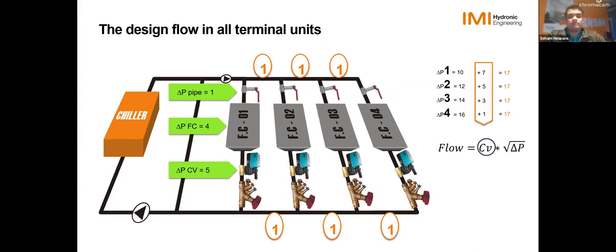And as I mentioned, it's based on what valve you're picking. It's the CV of the valve. It's the opening that you have on your valve and how much you restrict it. So, the closer you get to the pump, the more restrictions you're going to add, of course, because you want to have higher pressure drop. You need higher pressure resistance closer to the pump, because that's where you're possibly going to overflow. So, it's just going to be more closed as you get closer to the pump.